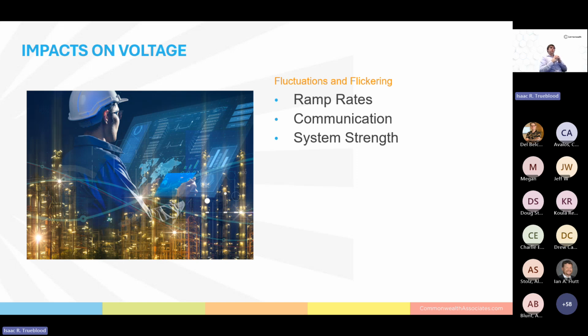So now I'll move on to impacts on voltage. I'm sure if anyone here works for or as a local utility, you hear every light flicker or refrigerator malfunction the customers may blame on any change they can see, everything from a changed fuse to a new substation. While some of these concerns may not be valid, distributed energy resources can cause unwanted voltage fluctuations and flickering. Having a source of generation that close to load means that generation increases and decreases can more easily cause voltage fluctuations that the system may not be capable of sensing or regulating. This can be especially true for customers near the end of the feeder.